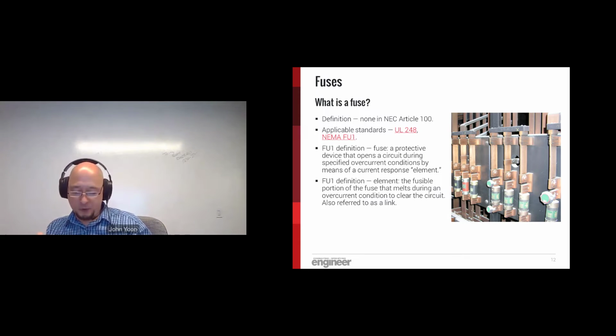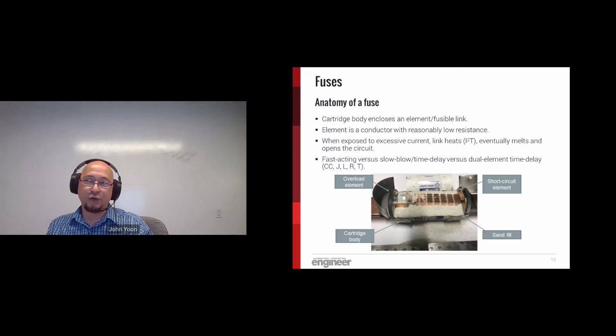There are two applicable standards for fuses, UL 248 and NEMA FU1. Let's start with the NEMA definition. A fuse is a protective device that opens a circuit during a specified overcurrent condition by means of a current responsive element. That element is the fusible portion of the fuse that melts during an overcurrent condition to clear the circuit. Basically, that's a sacrificial conductor that melts, maybe even vaporizes, depending on the magnitude of your current. When exposed to an overcurrent condition, it opens the circuit and prevents damage to those downstream devices.